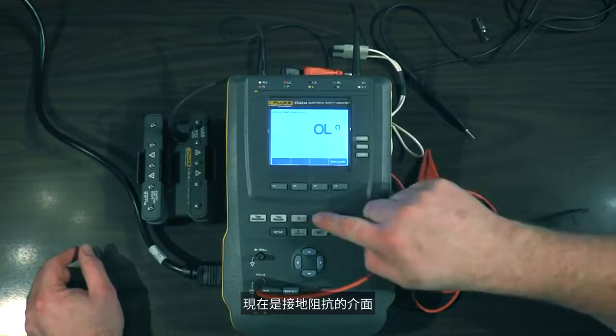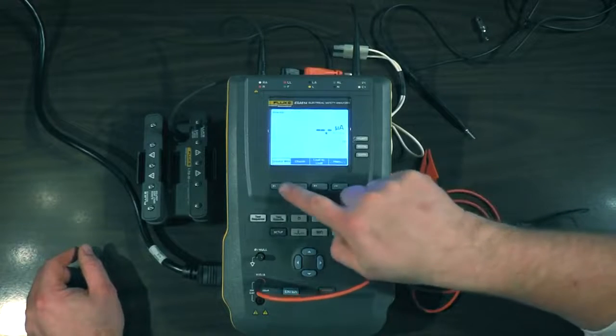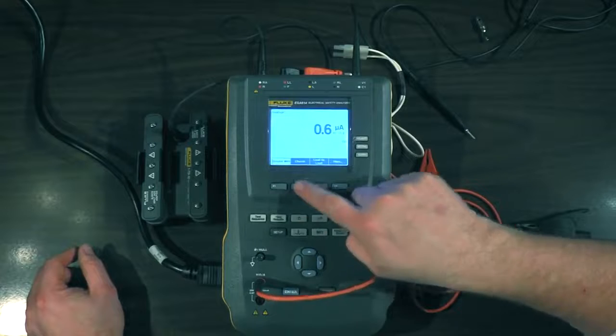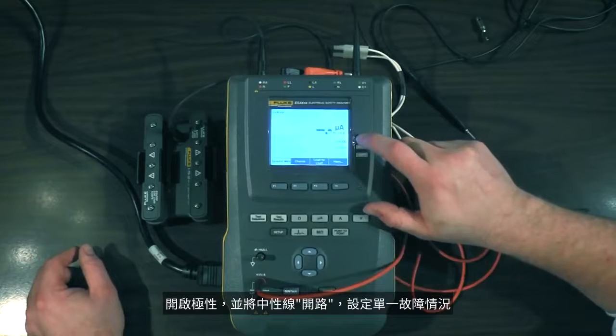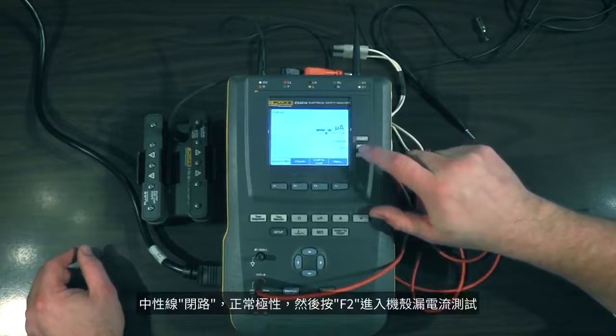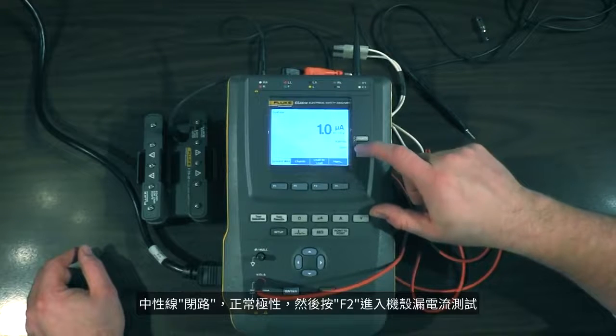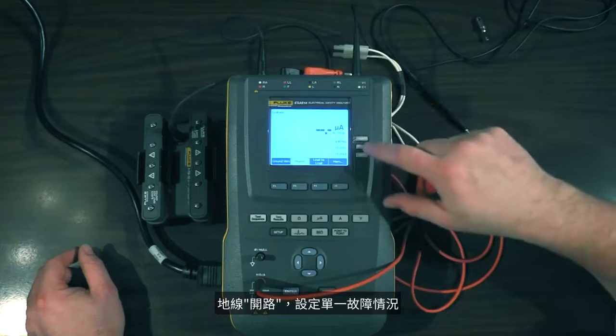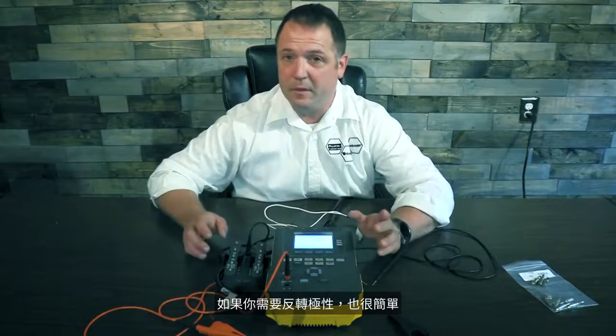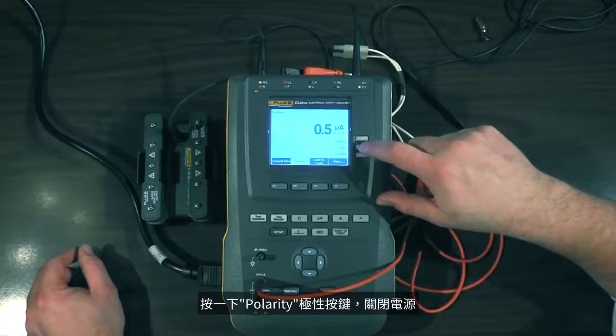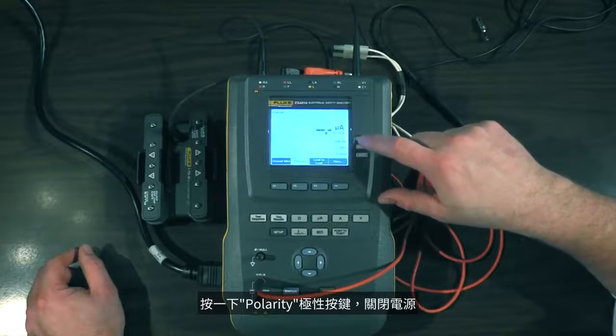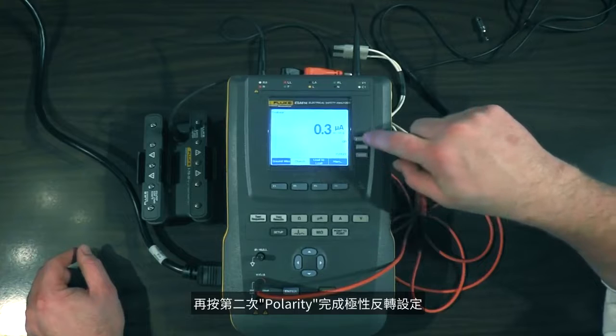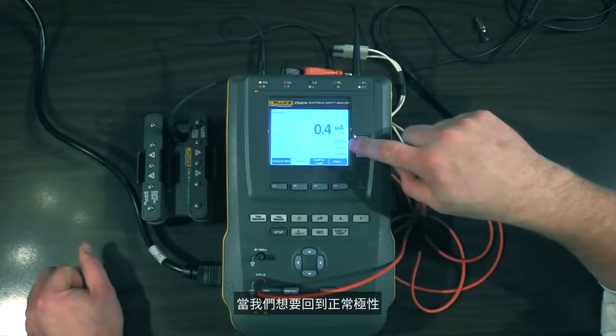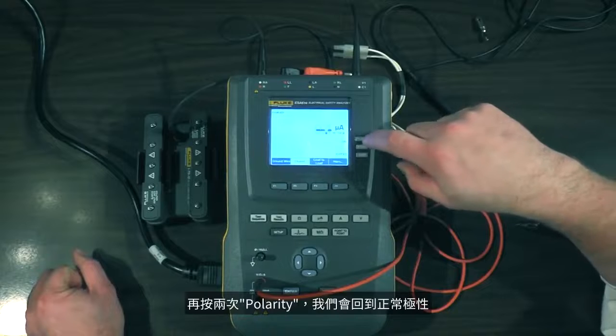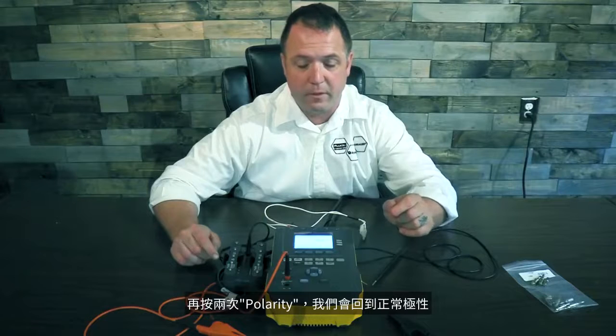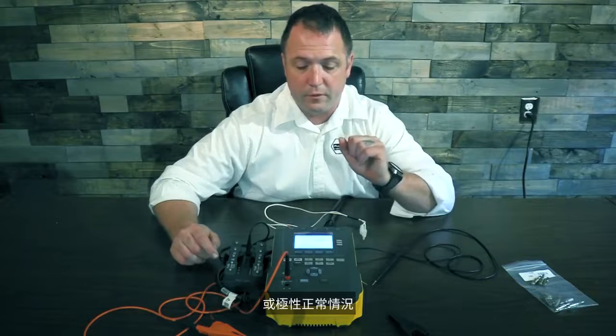So ground wire resistance. Back to leakage then. And we can do our ground leakage. Forward polarity. Open the neutral for single fault, close it, chassis leakage, normal polarity, open the earth for single fault. If you do reverse polarity testing, simple enough, and any of these tests, just simply push the polarity button once to off, and then a second time to reverse. So, and then we can go back to normal polarity. So then we'll close and we'll have normal polarity, or forward polarity, normal conditions.